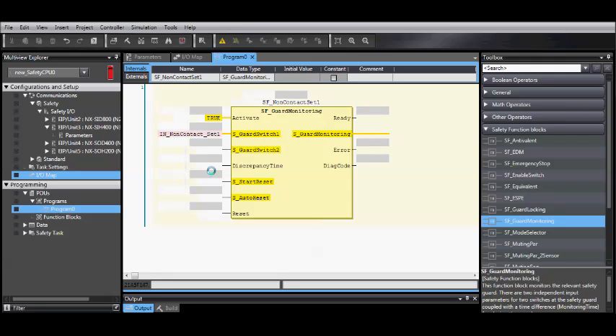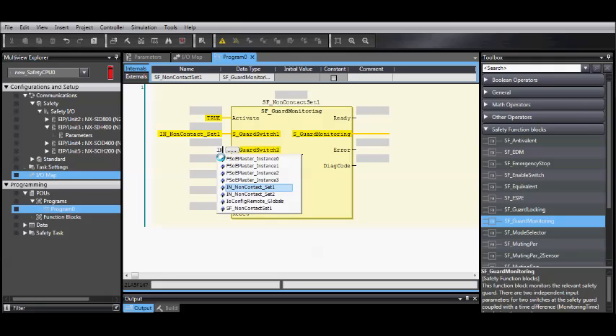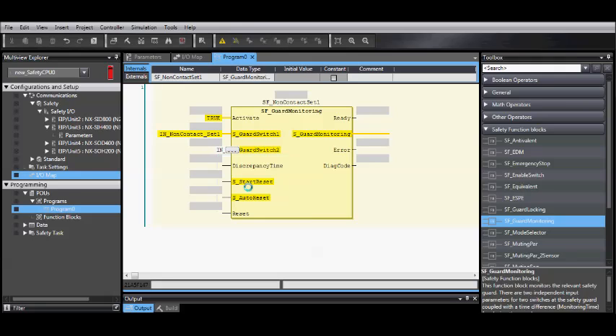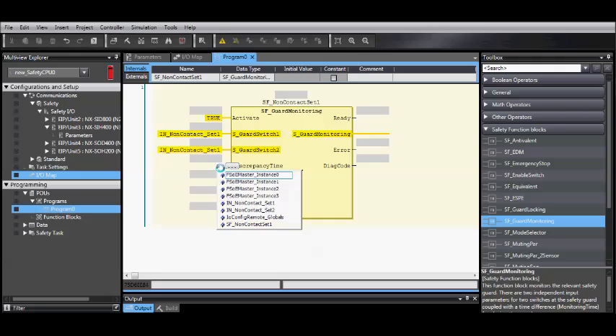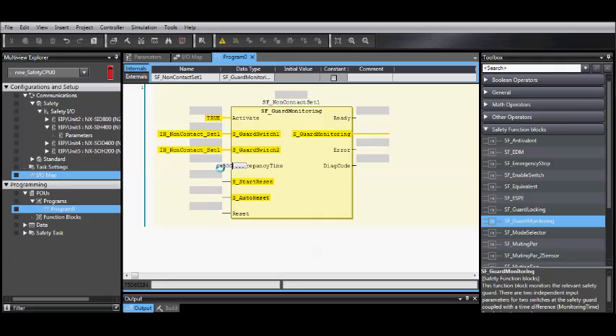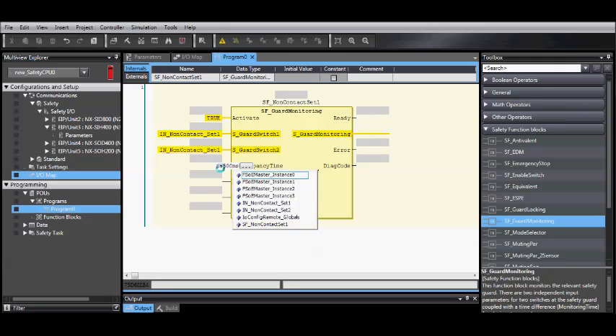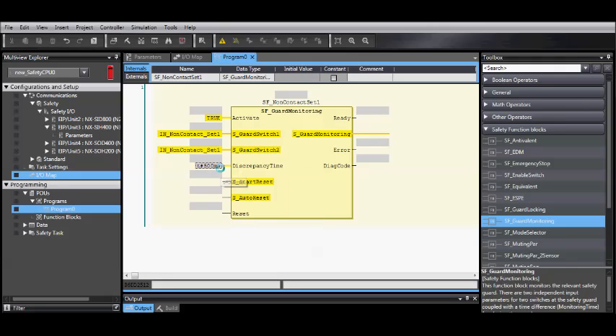For the Guard Switch 1, you want to select the input for the first set only, and you also need to repeat this for the second channel. For discrepancy time, T, pound, 500 milliseconds, and then add your reset button.